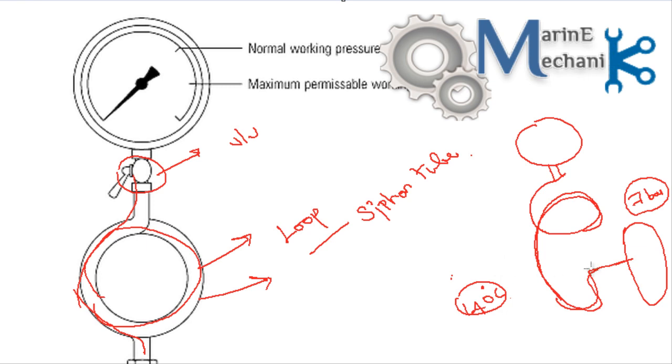If there is no loop, if the tapping is going to be straight from the boiler, no loop, just straight from the boiler, the steam or water which is at 140 degrees celsius just goes and hits the bourdon and then it might be a problem for it or it might get damaged.